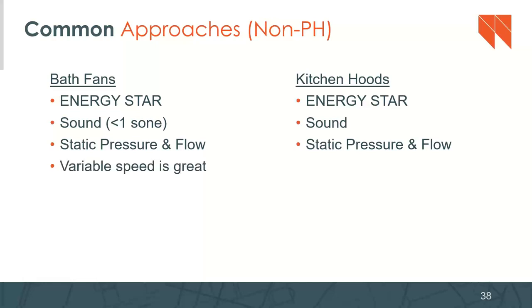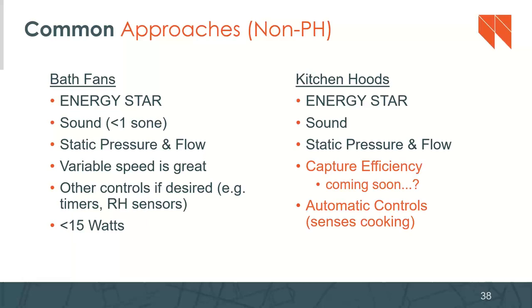But yeah, for the typical approach, this is kind of our recommendations. Variable speed's great. Other controls for bath fans include timers and relative humidity sensors. Trying to find a piece of equipment that's less than 15 watts is a good idea, and you'll be able to see what that rating is on the Energy Star certified stuff. In terms of the kitchen hoods, capture efficiency may be coming soon. It's being talked about within the industry, but certainly not required and not a thing yet. And then maybe automatic controls for the kitchen range to turn on when it senses that cooking is happening could potentially be a thing.